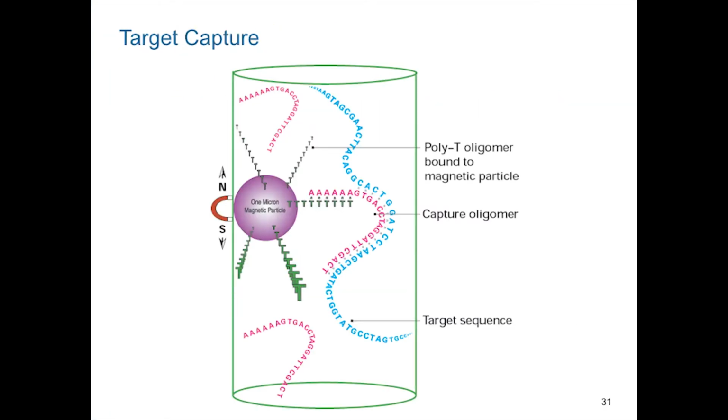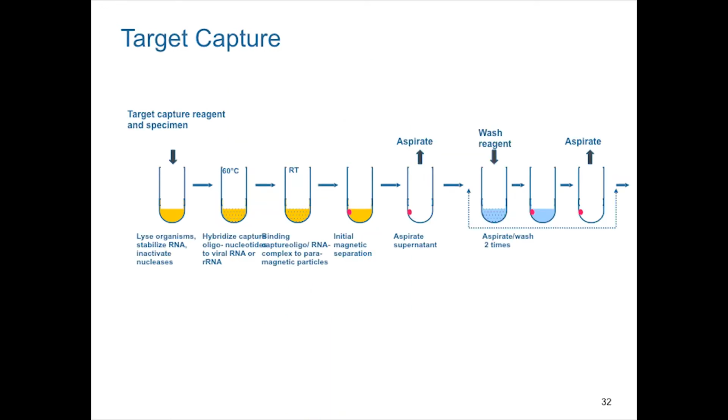So layer into this. So this is now an onion story. You start off with the single core of the onion, you start putting layers on to make further improvements. As time goes on, we want to detect a lot more than bacteria with ribosomal RNA. We want to detect viruses. We need amplification. We need better ways to clean the nucleic acid up. So this was a specific target capture, specific target sequence here, and a poly A tail for capture with a poly dT bead. What was nice about it is we could configure it such that once the sample was concentrated on the magnetic beads, we could do all the washes, the magnetic separations, et cetera, in that single tube.